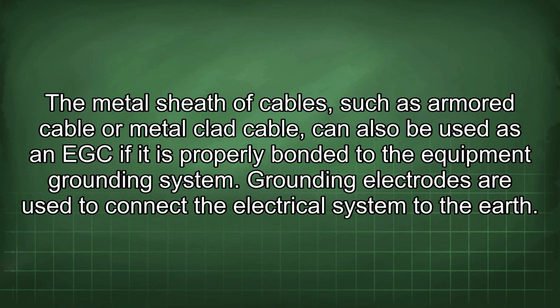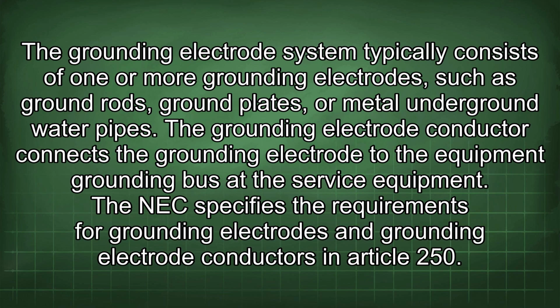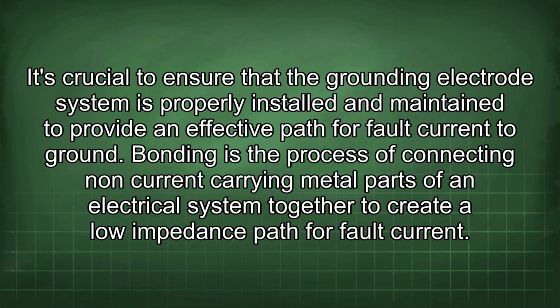The metal sheath of cables, such as armored cable or metal-clad cable, can also be used as an EGC if it is properly bonded to the equipment grounding system. Grounding electrodes are used to connect the electrical system to the earth. The grounding electrode system typically consists of one or more grounding electrodes, such as ground rods, ground plates, or metal underground water pipes. The grounding electrode conductor connects the grounding electrode to the equipment grounding bus at the service equipment. The NEC specifies the requirements for grounding electrodes and grounding electrode conductors in Article 250. It's crucial to ensure that the grounding electrode system is properly installed and maintained to provide an effective path for fault current to ground.